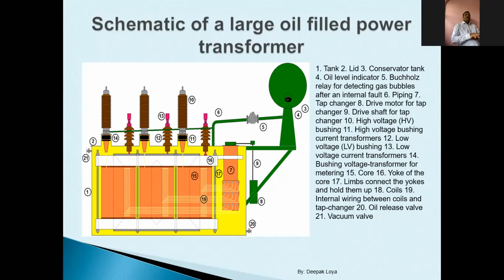When I am using a liquid inside a transformer, which is a sealed equipment, then when the temperature of this fluid increases, it will expand. And when it is cooled, it will contract. So there will be movement in the volume of this liquid. It will go up or it will go down. If that is a sealed tank, it will be a problem. When my transformer oil temperature increases, the oil will expand. This will create extra pressure on my tank. So either I will have to increase the mechanical strength of my tank to withstand that pressure, or I will have to have some mechanism to absorb this expansion or contraction.